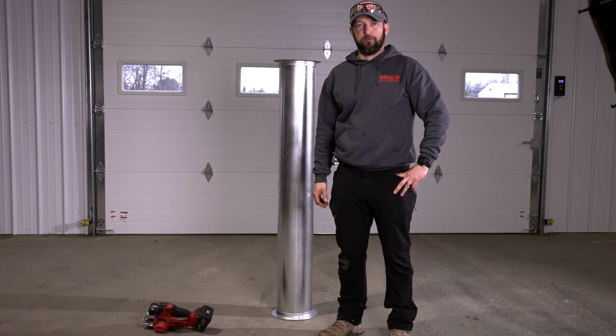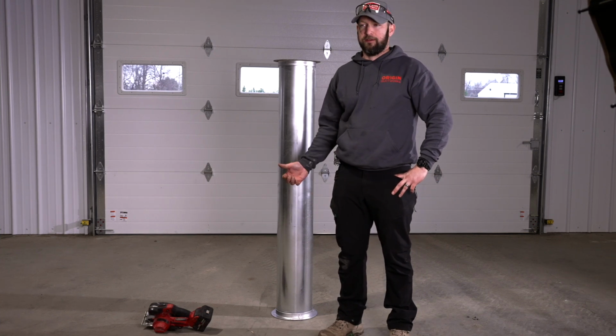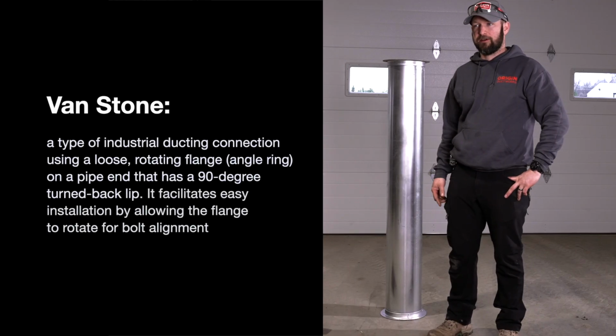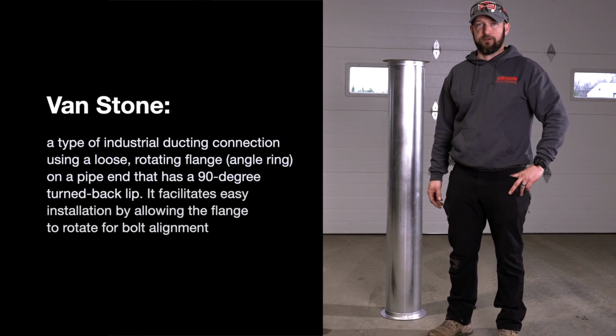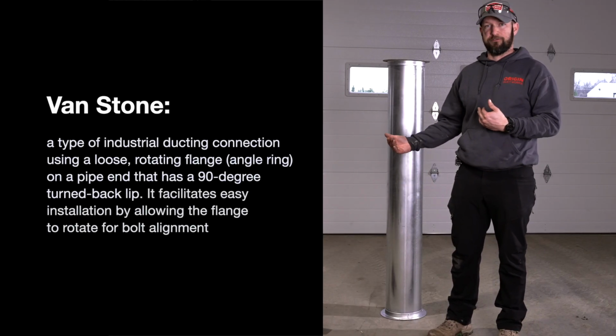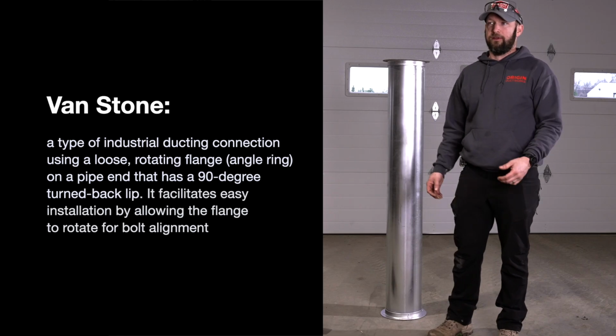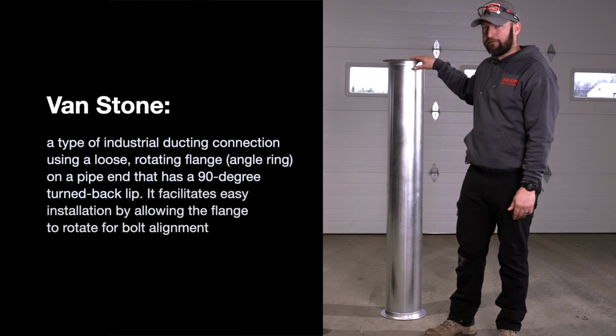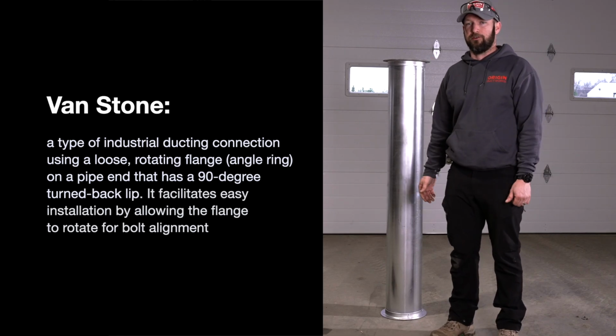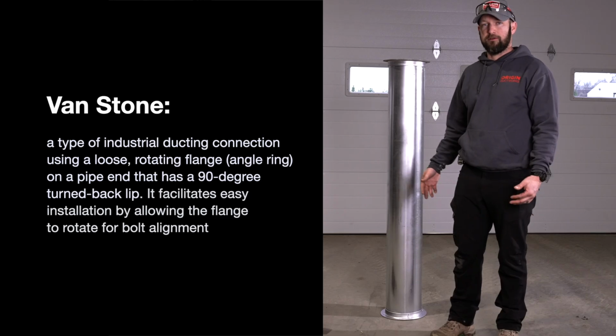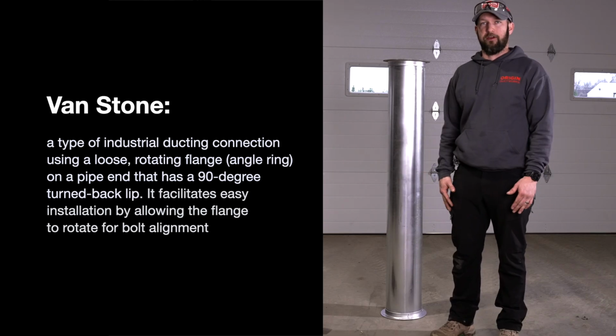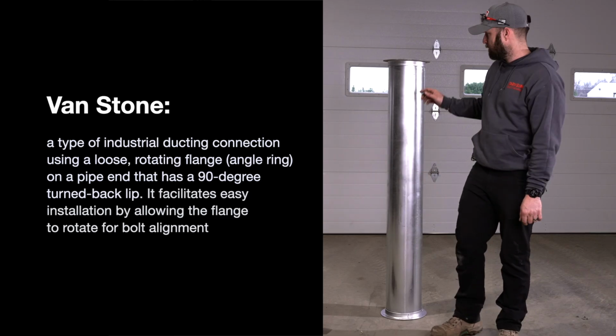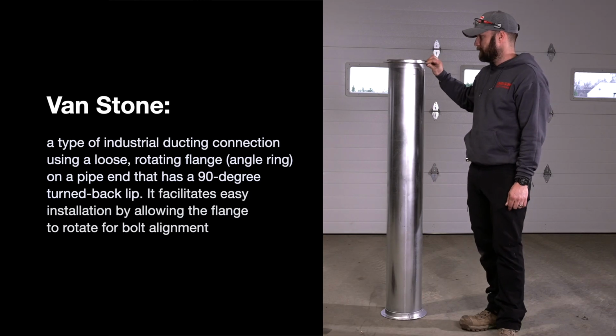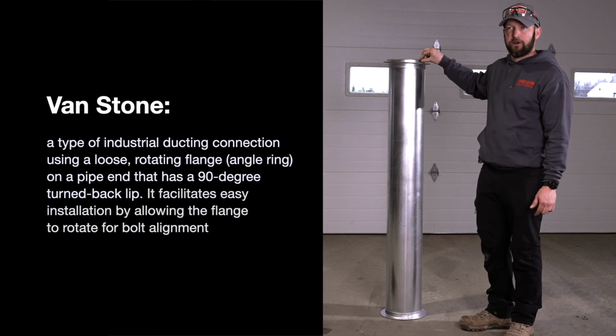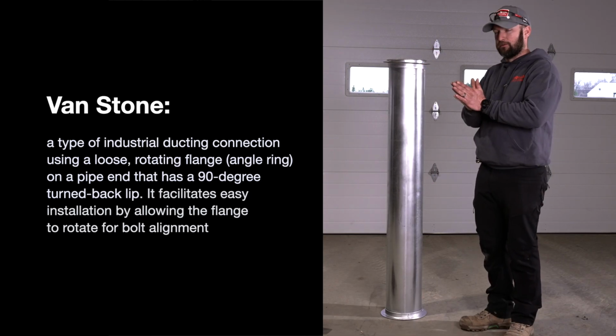I'm the lead install manager for Origin Ductworks, and today I'm going to go over the tools necessary and how to hand Van Stone ductwork so you can size your ductwork to fit in the field. It's very rare that a full length 5-foot piece of ductwork is going to fit where you need it, so you're going to need to know how to shorten the ductwork to fit into the area that you need. Hand Van Stoning is simply just recreating the factory folded edge so your pieces of ductwork will seal together.